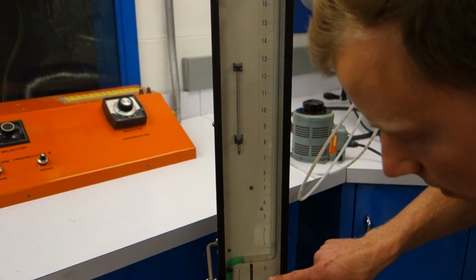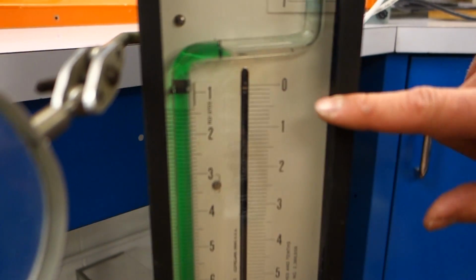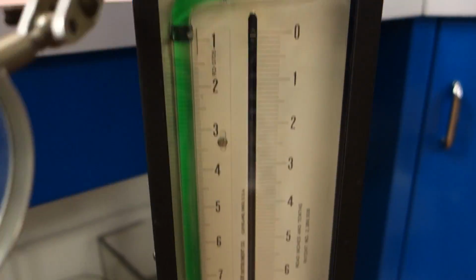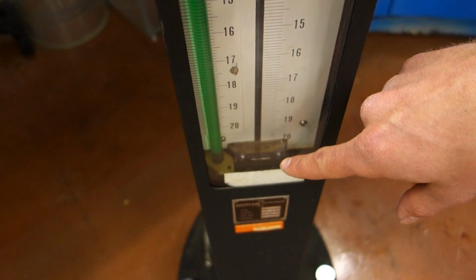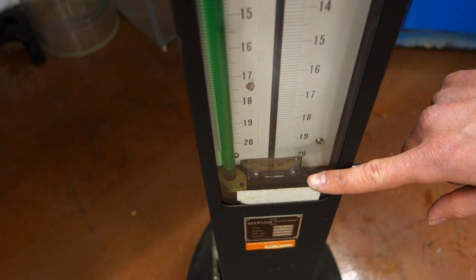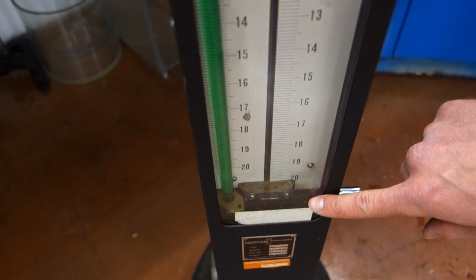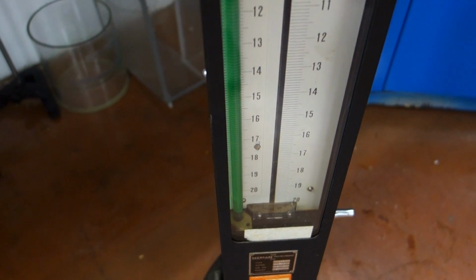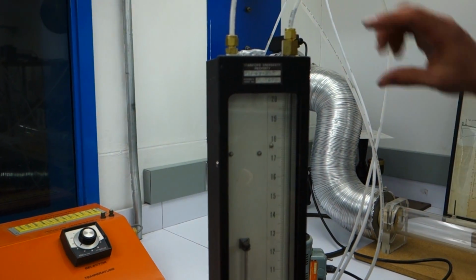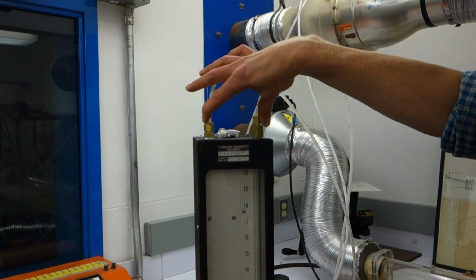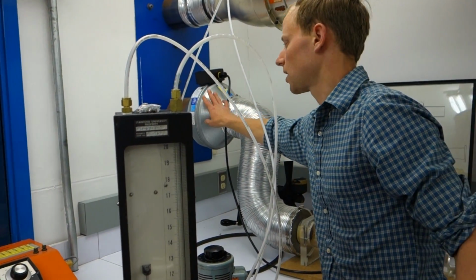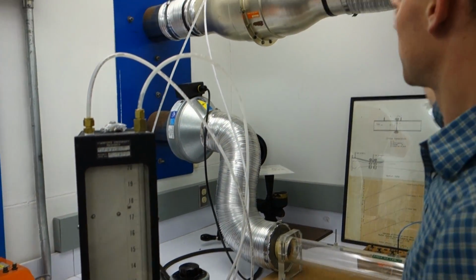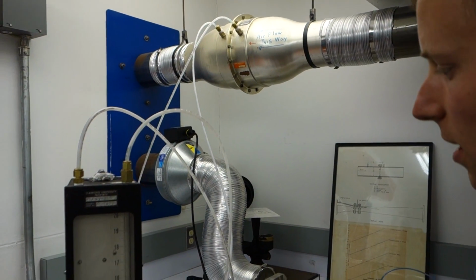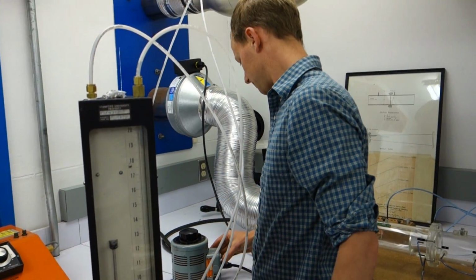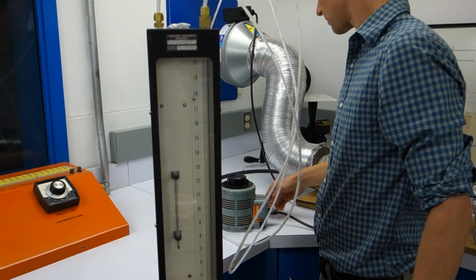And there is a reading on this device. It looks like it's reading 0/10 of an inch. And then down here at the bottom, there's another dial, which is reading 56/1000 of an inch. So right now we would be at 0.056 inches. That's our zero level. Now I would apply a pressure differential across the taps via our blower here, which is sucking in air from the lab through the tubes and around. So we'll do that real quick after we plug it in.